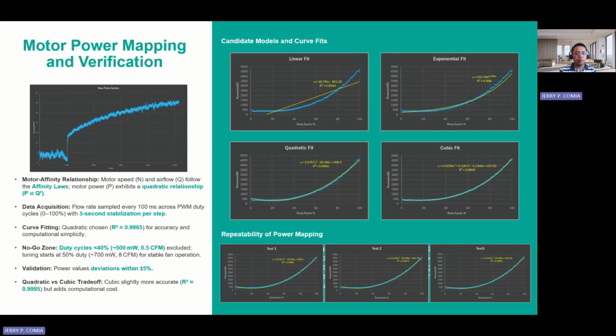This slide shows the motor power mapping. This is essential because it helps us understand the nonlinear relationship between the motor's electrical power input and the airflow rate. This means that we can directly predict airflow just from the power input without modeling the complex behavior of the motor. During the characterization phase, the system sampled airflow every 100 milliseconds, while the PWM duty cycle was varied from 0 to 100%. Each step was allowed to stabilize for 5 seconds to ensure reliable measurements.